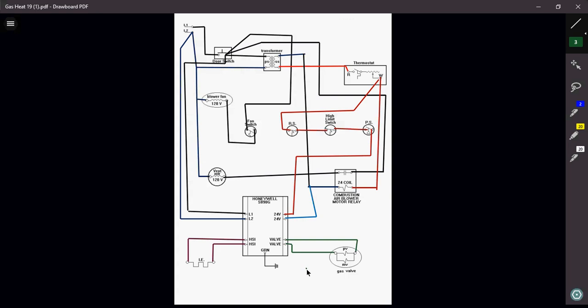One thing that I do want to add to this diagram is that a lot of your modern and more recent hot surface ignition furnaces, high efficiency stuff like that, may not necessarily have a temperature actuated fan switch integrated on the furnace itself. Some of your modern stuff now has an integrated timer that will turn the blower on. Usually located on the circuit board itself is a set of dip switches. You just set the dip switch to either 10, 20, 30 seconds, and based off of time, that switch will now close, and that's what actually brings on the blower motor.